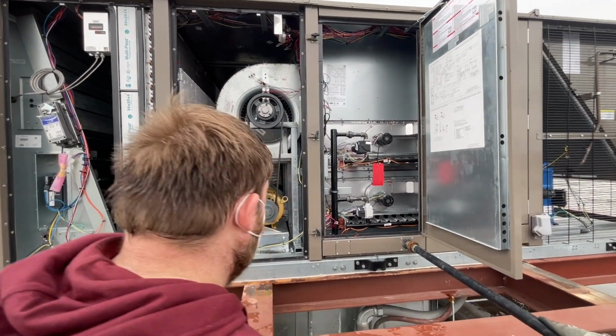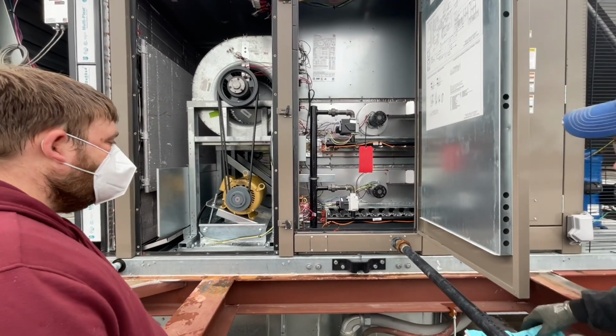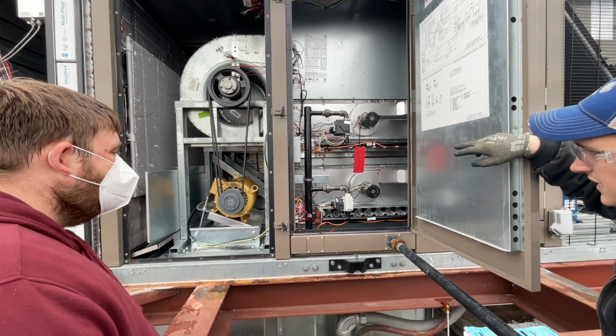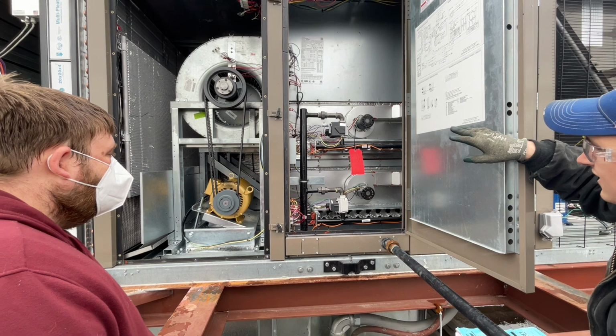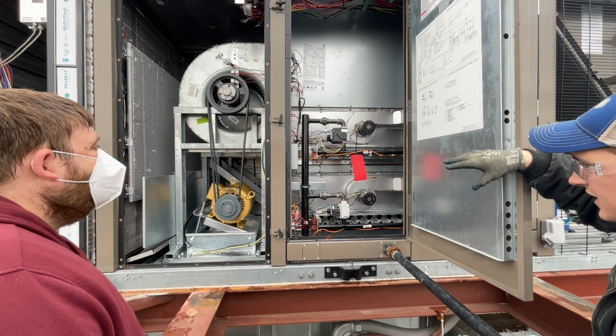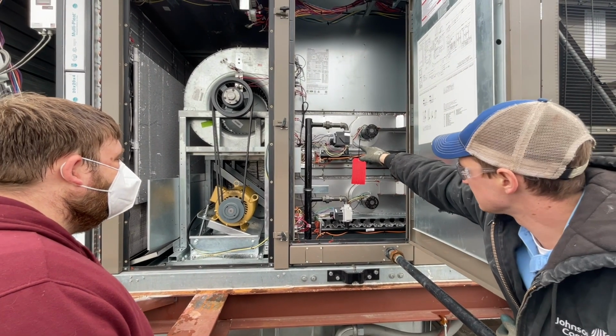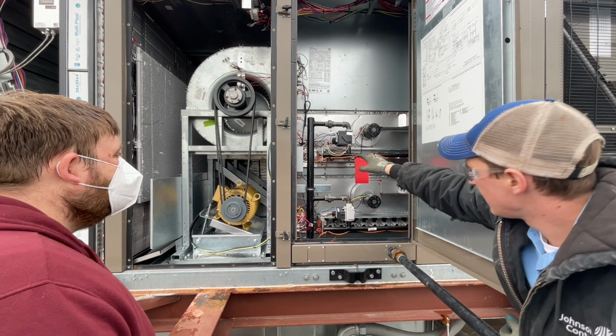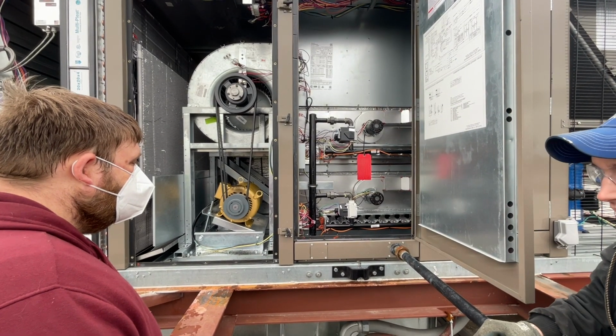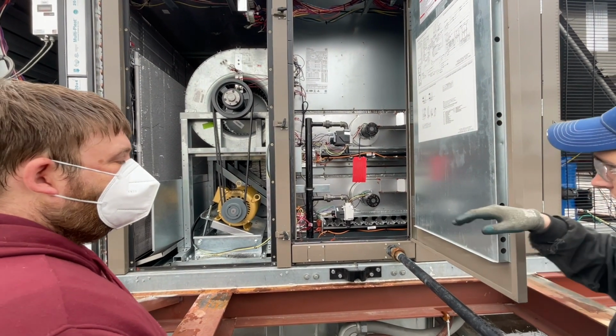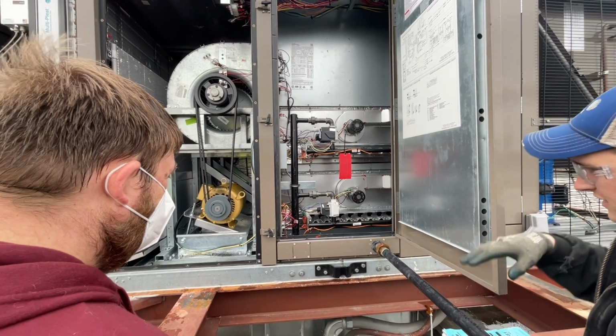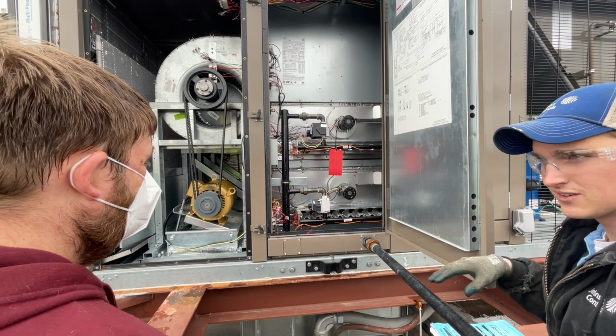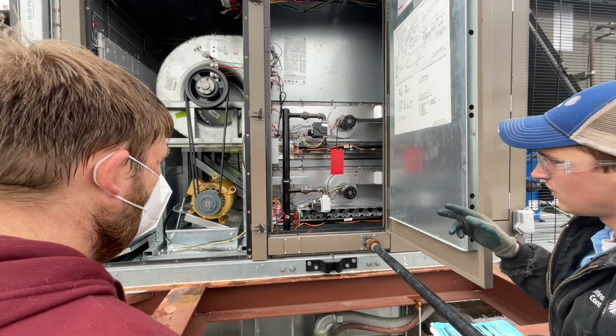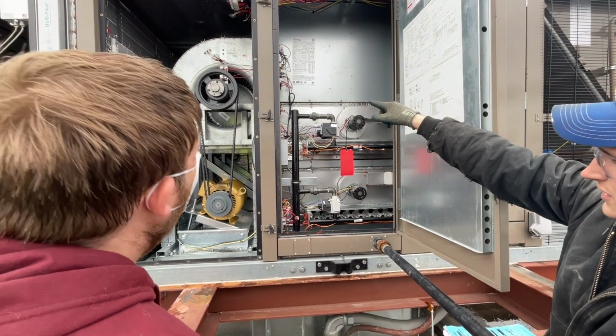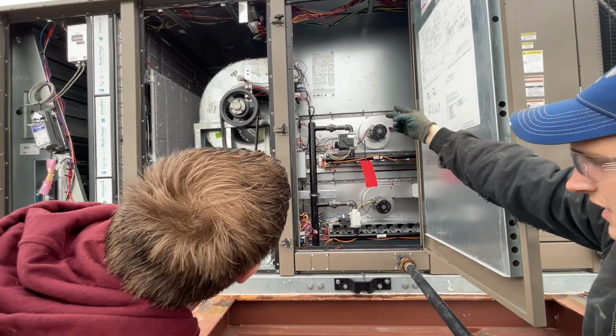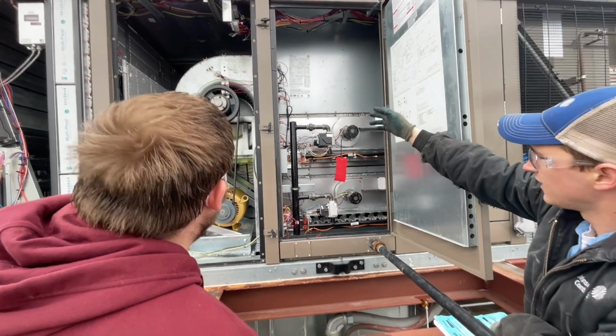In here we have our heating section. So gas heat, we have a modulating heat board. This gas valve right here is modulating along with that inducer motor. So you're going to have a really high turn down rate. It'll run really low, and what's going to happen is, based on how far from set point you are downstairs on the thermostat, it's going to tell this board up here whether you need first stage of heat or second stage of heat, or both running.